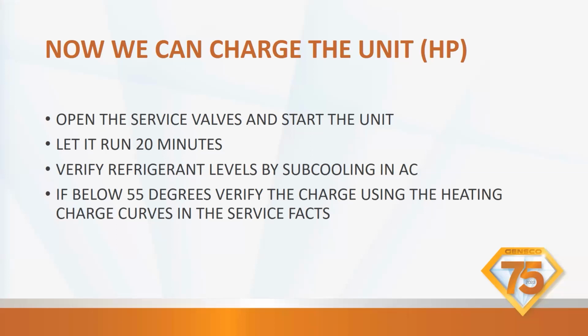Okay, and the reason that we need superheat is to prevent liquid refrigerant from getting to the compressor. That way we don't recondense our refrigerant in the line set getting back to the compressor, because we cannot compress a liquid. Okay, so that's basically the gist of superheat and subcooling.